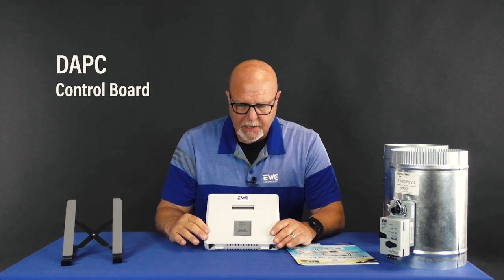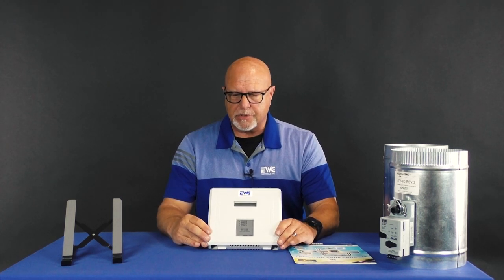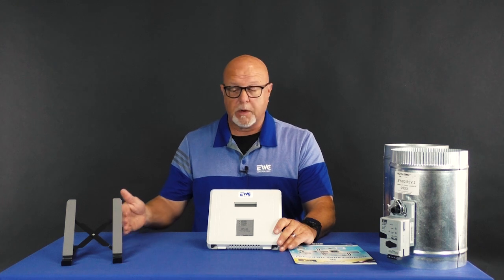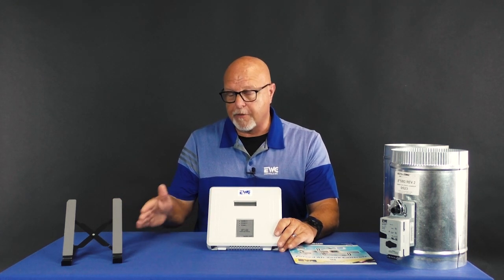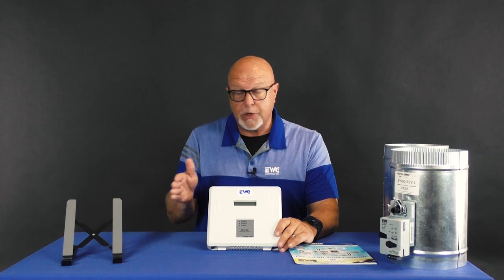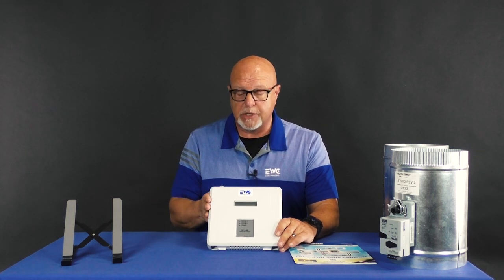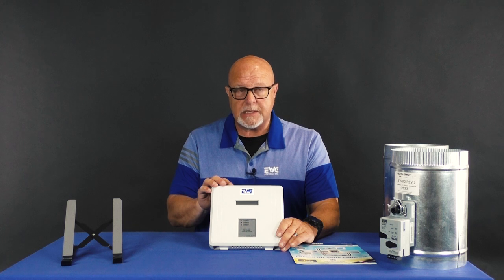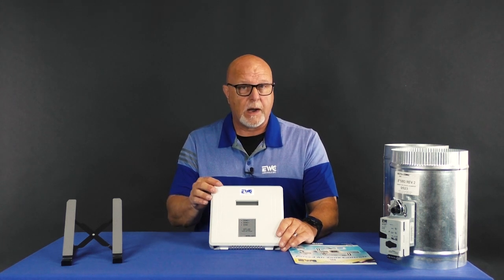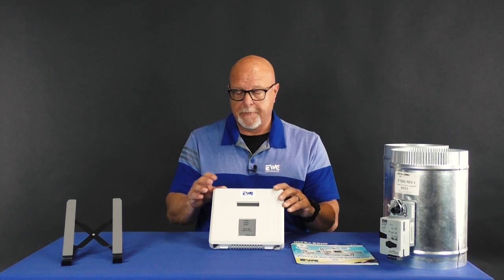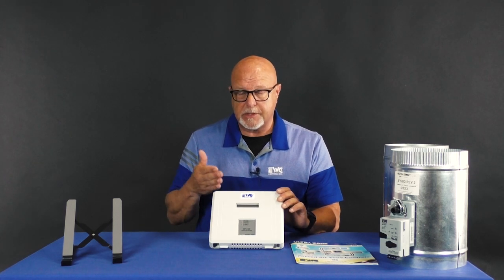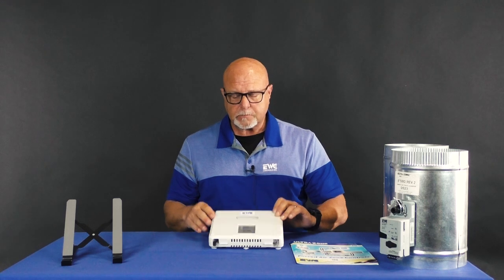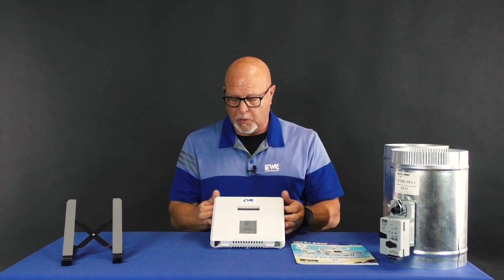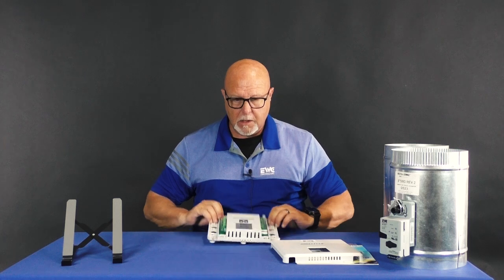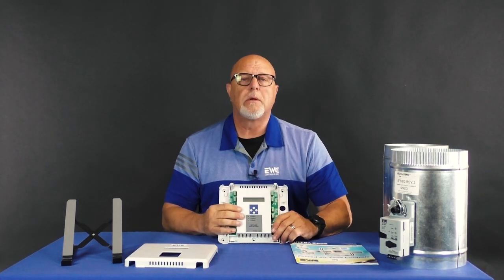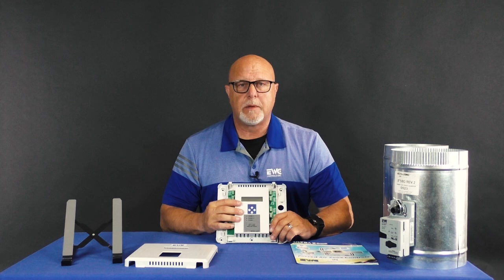The DAPC is a very unique feature board where, in addition to the zone board, you would wire the DAPC from the zone board to the DAPC. You're just powering it from the original zone board. And from this DAPC, you would bring your damper wiring from this board to the dampers. So from the board, your dampers to this board to the dampers. In the setup of this board, you will go into the menu and set up the board.